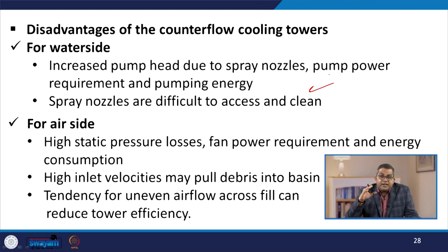Now, if we take the air side, then there are high static pressure losses, fan power requirement and energy consumption. The high inlet velocity may pull debris into the basin and thereby enhance microbial or biological activities. Then they may have a tendency for uneven airflow across the fill. This can reduce the tower efficiency.